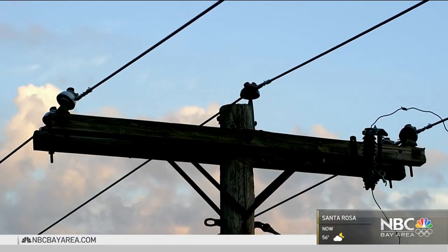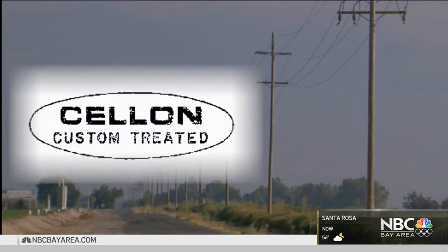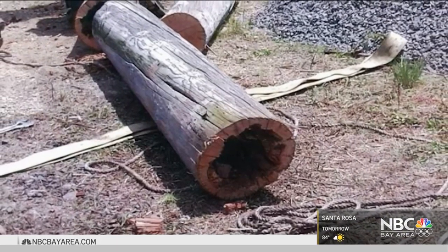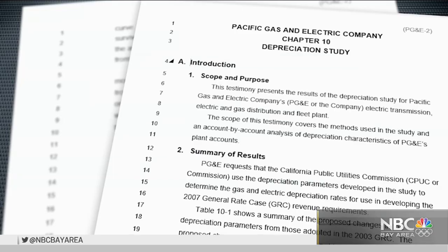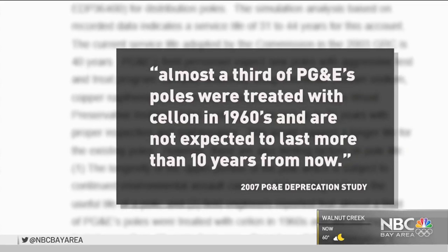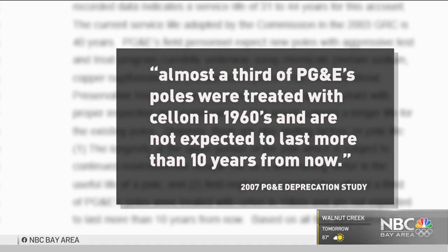The Danville pole, along with more than a half million other at-risk poles, all date back to before 1989. That's when PG&E stopped using Cellon, a highly toxic pesticide-laced gas, to prevent infestation from insects and the fungus that causes dry rot. The utility opted to use newer, more environmentally friendly methods, and the company knew the Cellon would only work for so long. In fact, in 2007, PG&E field engineers warned the aging poles wouldn't survive more than a decade.